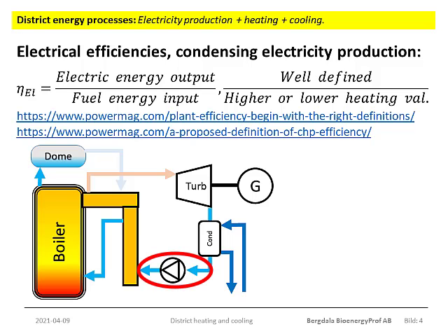So through a set of pumps, the pressure is raised back to 150 bar, and then the water is preheated in a set of heat exchangers and returned to the boiler walls for another round. The maximum amount of electricity is set by the difference between the steam pressure and temperature at the turbine inlet and the pressure and temperature in the condenser.